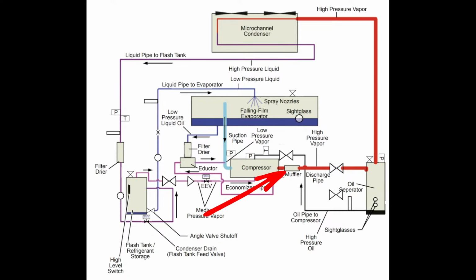So we have our compressor. This is our refrigerant circuit. We come over to our oil separator, through the condenser, and then back over to our flash tank. Okay, so we have a condenser drain valve, right? Which on the older models like the YCIV would have been referred to as a feed valve, but it's referred to as the drain valve in the YVAA series. So this happens through our flash tank economizer, goes through the economizing process, and then we had a fixed orifice right here on its way to the falling film evaporator.